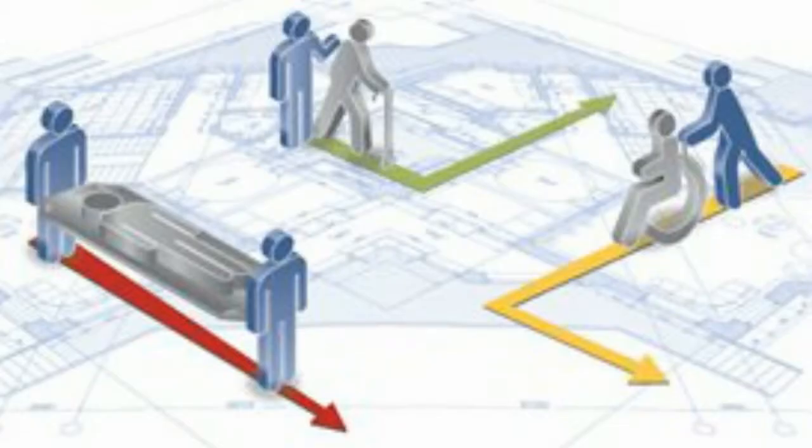If patient evacuation is required, the safest form of evacuation for employees and patients is horizontal evacuation. Horizontal evacuation involves moving down the corridor and into another smoke compartment or area of safety. Vertical evacuation is evacuation into and down a stairwell. Vertical evacuation should be used when horizontal evacuation is not possible.